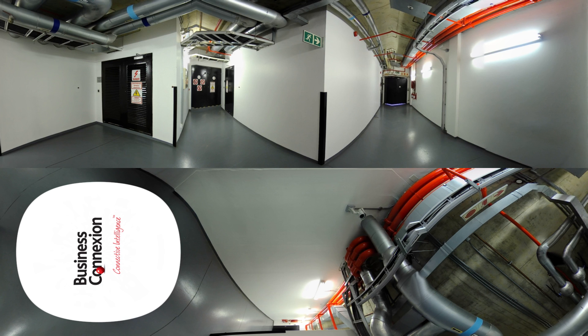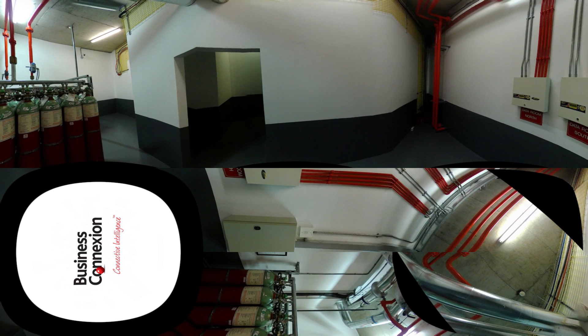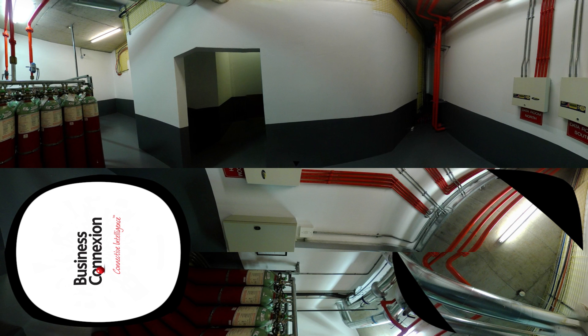Despite the complex system of water pipes and reservoirs, water is only a secondary guard against any fires. As the first line of defense, we have installed a complete gas-based fire suppression system. Both the water and gas fire suppression systems are divided into zones, which means that the system will only be activated in the zones where a fire has been detected, thereby protecting any sensitive equipment in other areas. The fire suppressant system uses argonite gas, a gas which takes enough oxygen out of the air to kill a fire, but still allows humans to breathe. Every month we pressure test the argonite tanks to ensure that they are ready for any eventuality. All crisis systems are also connected to the Gauteng Emergency Services, which means that the data center will automatically notify the fire department if any emergency is detected.